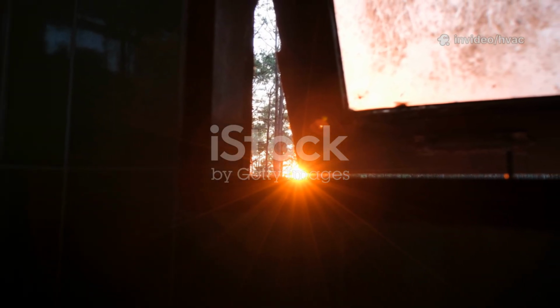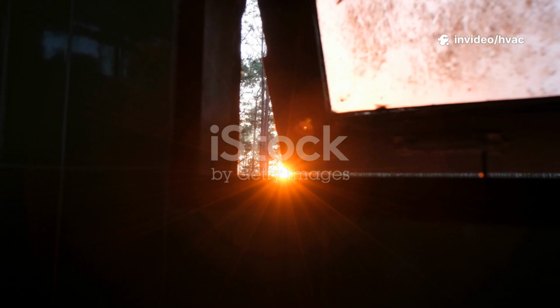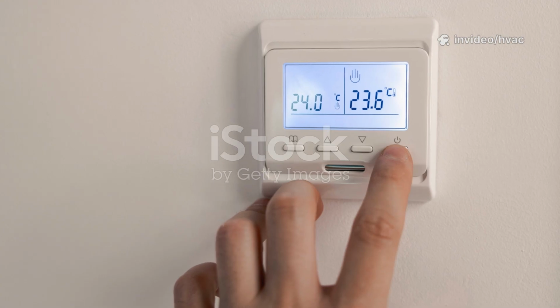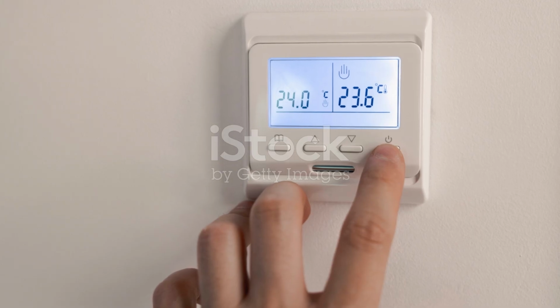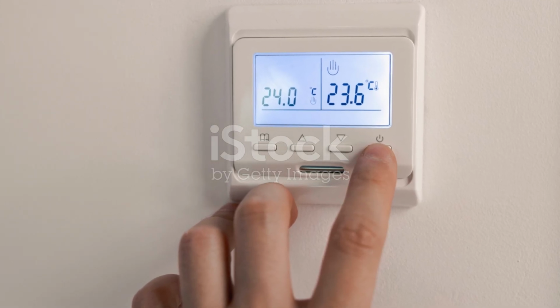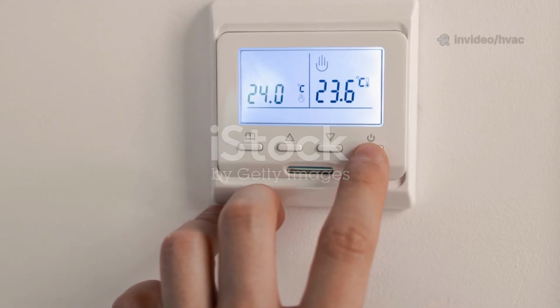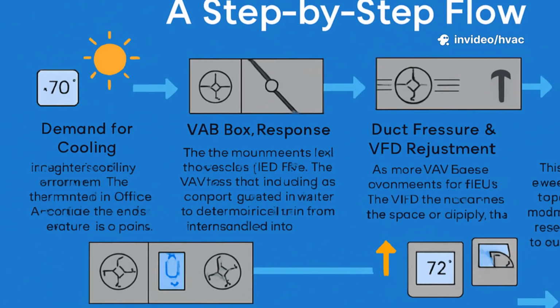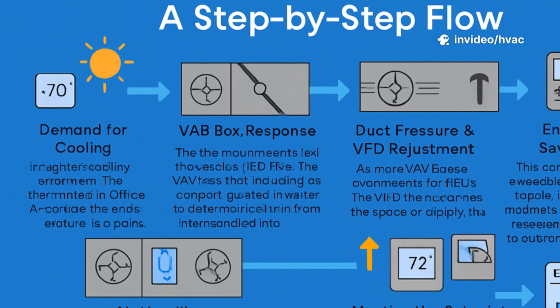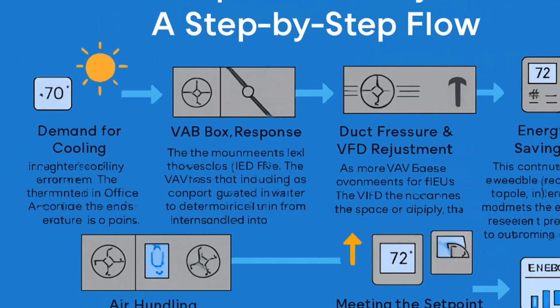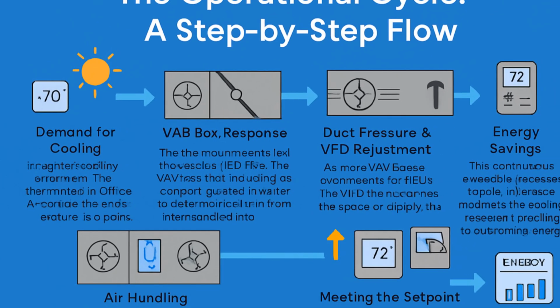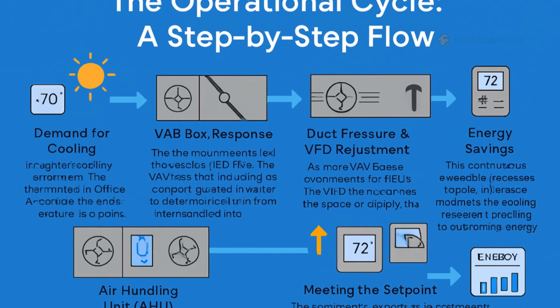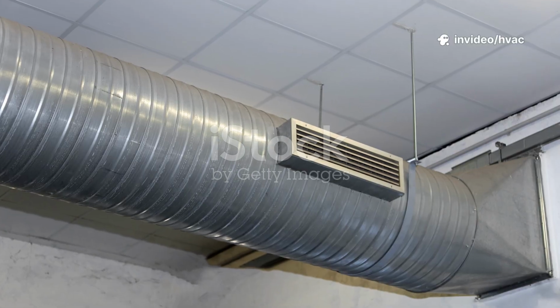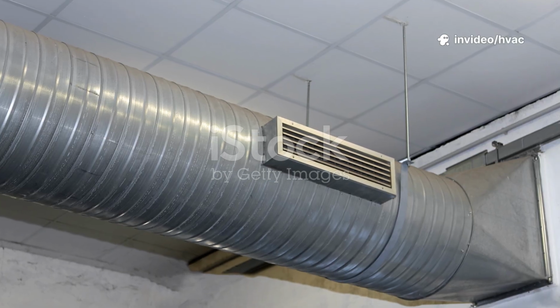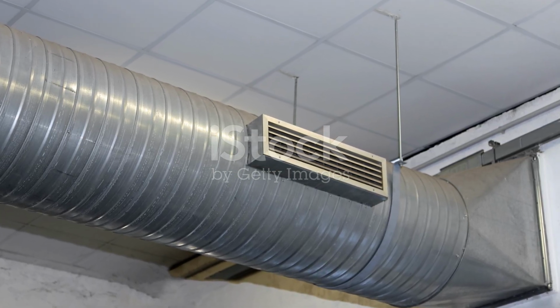Sunlight pours through the windows, quickly warming up a corner office. The temperature in that space starts to climb, making it noticeably warmer than the rest of the building. The thermostat on the wall senses this temperature rise almost instantly. It's always on the lookout for changes, and as soon as it detects the heat, it sends a signal to the VAV box above the ceiling. The VAV box responds by opening its damper wider, allowing a greater flow of cool, conditioned air to rush into the room. This extra burst of cool air helps bring the temperature back down to a comfortable level. Meanwhile, in other sunny spots throughout the building, more VAV boxes are doing the same thing, opening up to let in more cool air.